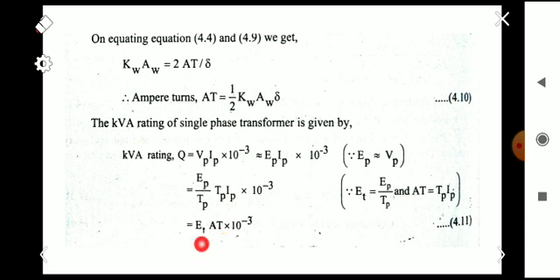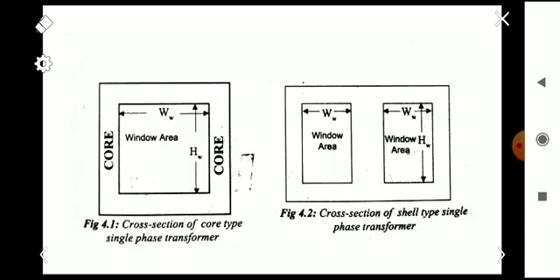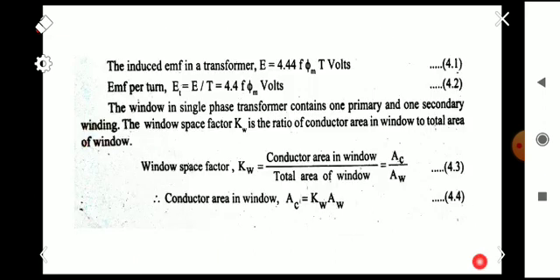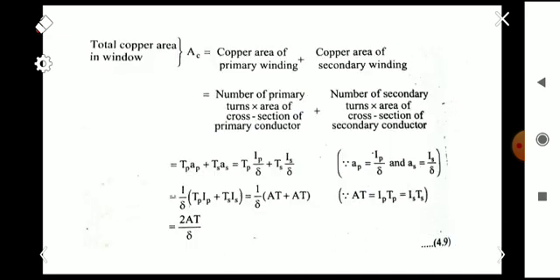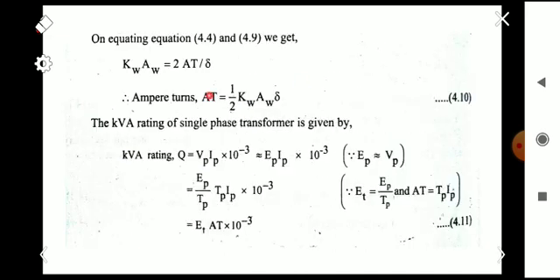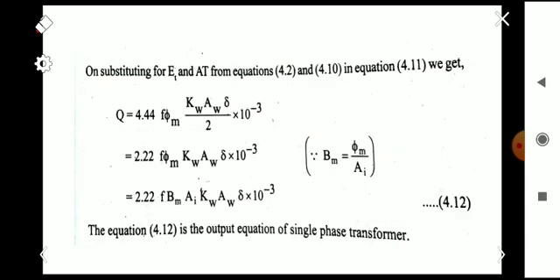We now substitute for E_T and AT. E_T = 4.44 f Φm, and AT = (1/2) K_w A_w δ. Substituting these into Q = E_T × AT × 10⁻³, we get Q = 4.44 f Φm × (K_w A_w δ / 2) × 10⁻³. Simplifying, Q = 2.22 f Φm K_w A_w δ × 10⁻³.